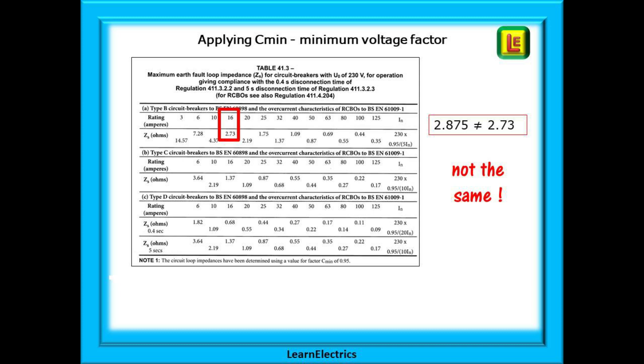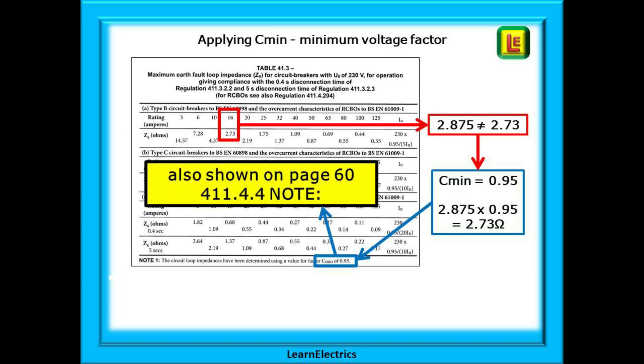Compare this to table 41.3 on page 62. Find the type B section. Find 16 amps and the answer shown does not match our calculation. 2.875 is not equal to 2.73. We need to do another calculation to get the right answer.